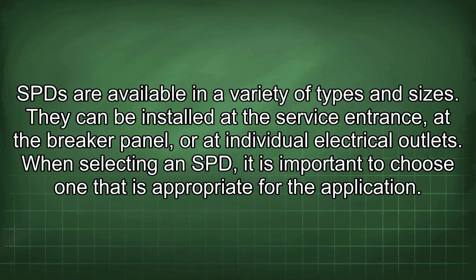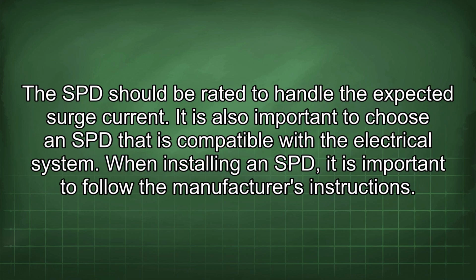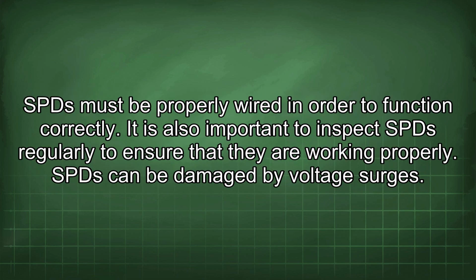When selecting an SPD, it is important to choose one that is appropriate for the application. The SPD should be rated to handle the expected surge current. It is also important to choose an SPD that is compatible with the electrical system. When installing an SPD, it is important to follow the manufacturer's instructions. SPDs must be properly wired in order to function correctly. It is also important to inspect SPDs regularly to ensure that they are working properly.